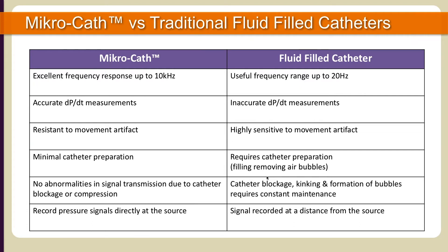There are many advantages to utilizing the Mikro-Cath for its high-fidelity pressure signal. Millar sensors are considered the gold standard for in vivo and in vitro pressure measurements. The sensor's diaphragm is extremely sensitive to small pressure changes. Compared to fluid-filled catheters, there is no motion or catheter whip artifacts. Millar sensors have an excellent frequency response and no signal attenuation. The sensor is also vented to atmosphere to minimize the effect of atmospheric pressure.